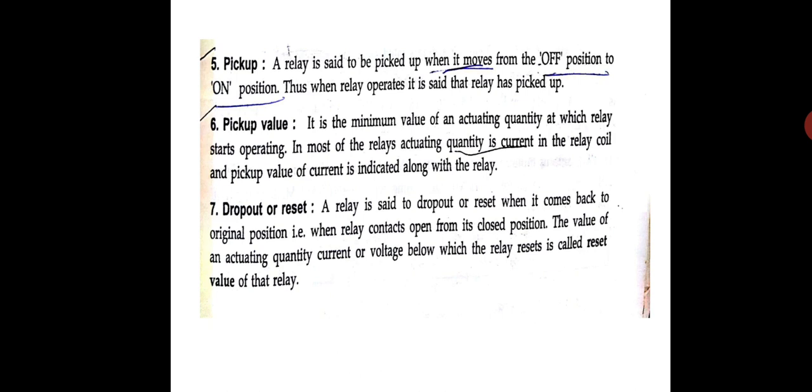Again, it depends on how much setting you have kept, how much percentage setting you have kept. For 10.1 amperes it should not operate. It should not even operate for 11 amperes. After 10, 11, for 12, 13 it should operate. So for which current, try to understand, for which first current it operates, that is called the pickup value.